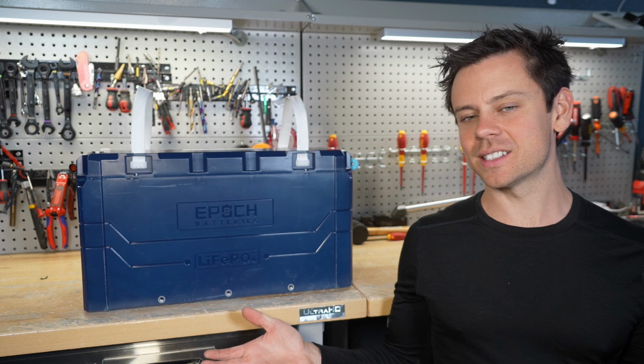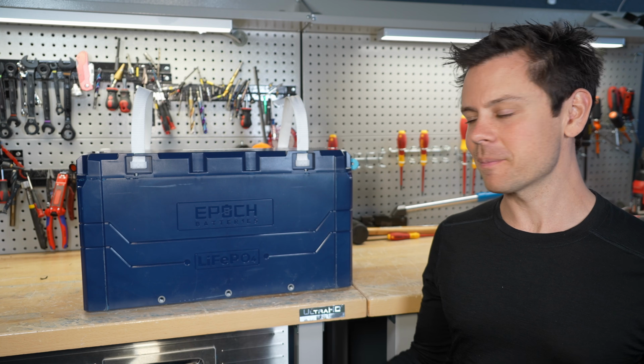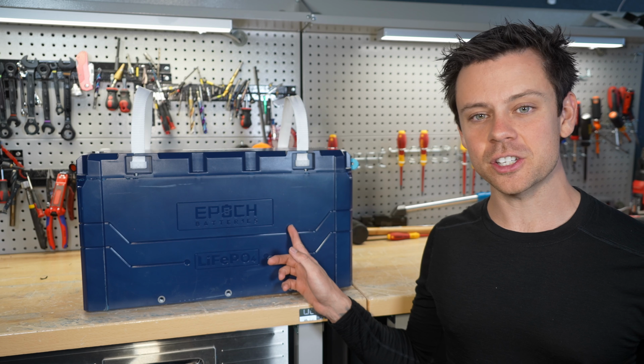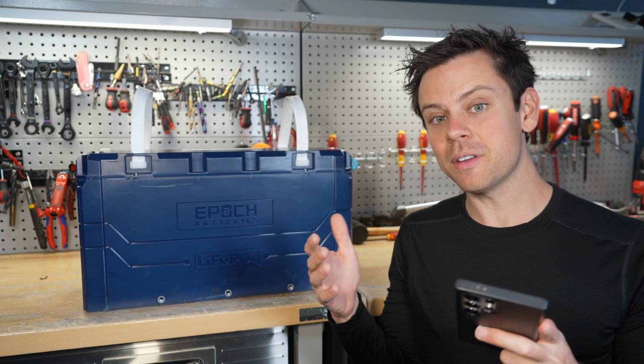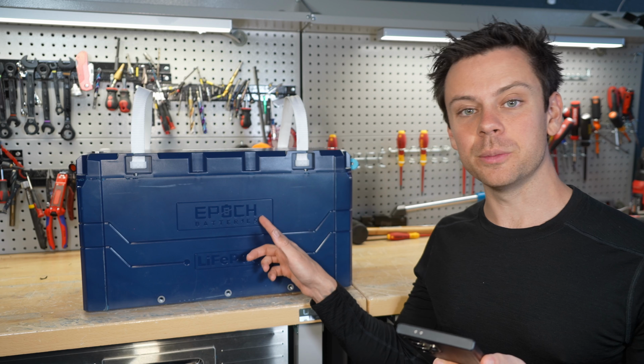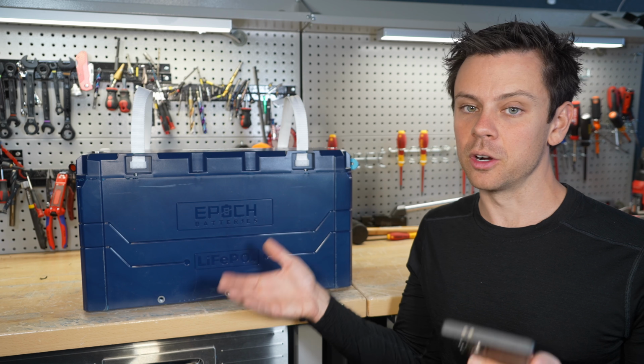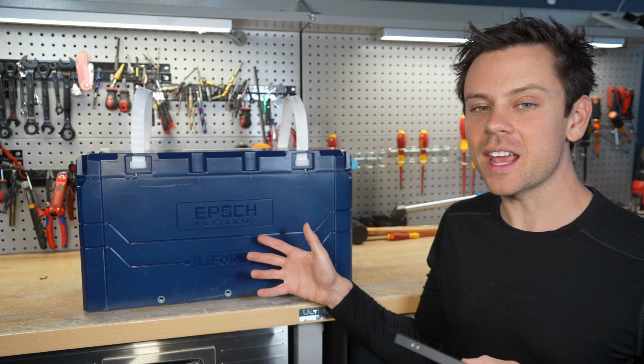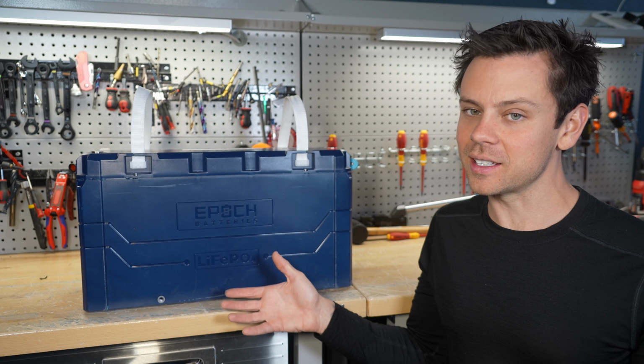Now that the initial testing is done, what should we think about this battery? First off, version 1 had a lot of issues. For example, on the forum, people were having balancing issues. Also, when you use the communication with Victron, there was a problem with over voltage protection. And then when the over-the-air update came out on version 2, that had issues as well.